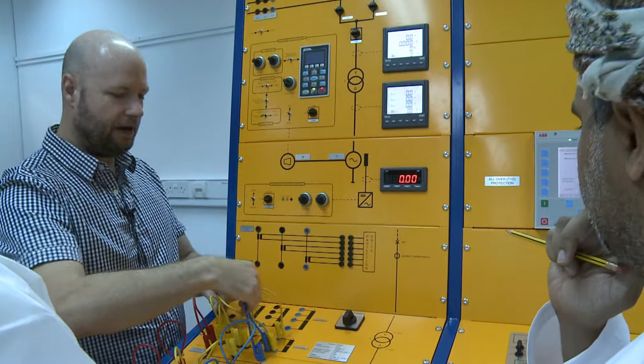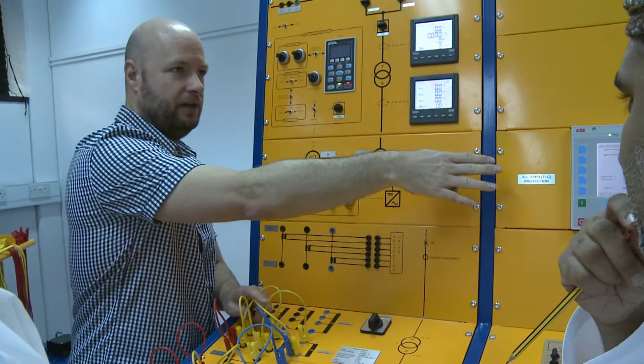This unit for the differential needs to know the clock of the transformer. It's programmed for, at the moment, 5 o'clock, so depending on how this one is connected, it will be right or wrong. So we will tell as soon as we start to load, it might trip. And if it trips, we know that we need to either change the clock here or change this one here.